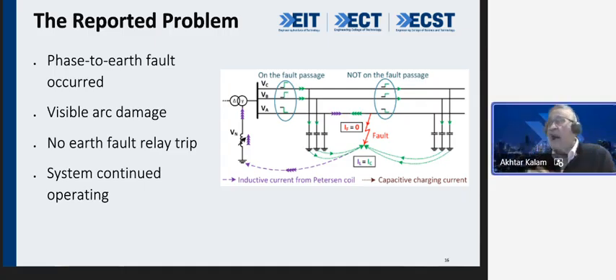There will be visible arc damage, but the earth fault relay did not trip. And the system kept on operating. In spite of having that fault, my friend, the system kept operating. In fact, the fault was there. Electrically, it was faulted. The system behaved as if nothing had happened. That could be very dangerous, my friend. It could be fatal too. This is the problem that is there, right?